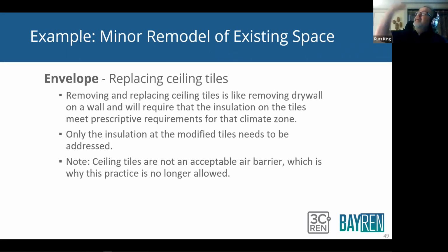Replacing ceiling tiles. Think of a T-bar ceiling as like the sheetrock on the wall, all right? If you open up T-bar ceilings, if you replace T-bar ceiling and there's insulation on the other side, it triggers the requirement just as though you were removing sheetrock from a wall, okay? So replacing ceiling tiles is like removing drywall on a wall and will require that the insulation on those tiles meet prescriptive requirements for that climate zone. Only the insulation at the modified tiles needs to be addressed. So if they're only replacing four tiles, you only have to insulate the top of those four tiles to what the requirement is. That's kind of unfortunate, but what are they going to do? If they replace four tiles, have to insulate the entire thing? So it's just those four tiles.